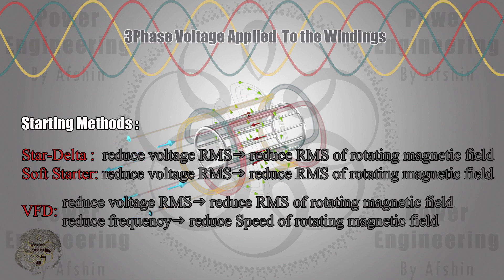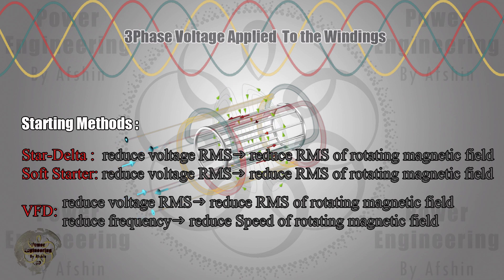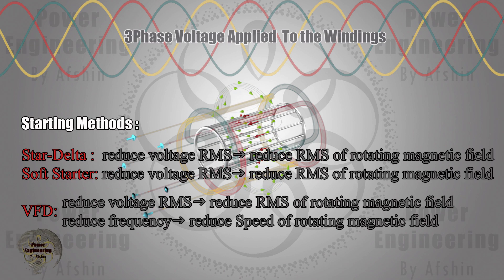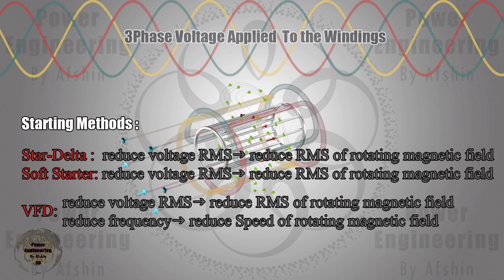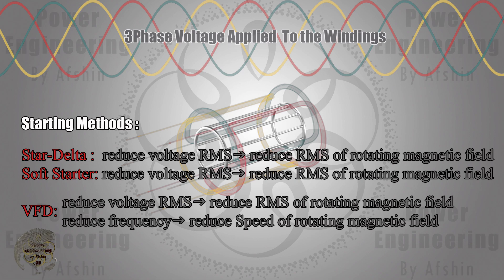In star delta and soft starter methods, reducing the input voltage reduces the starting flux, though the source frequency remains unchanged. The VFD method allows control over both input voltage and frequency, reducing both parameters during startup according to the VFD's control mode. Of course, using these starting methods requires studying the motor's mechanical load.